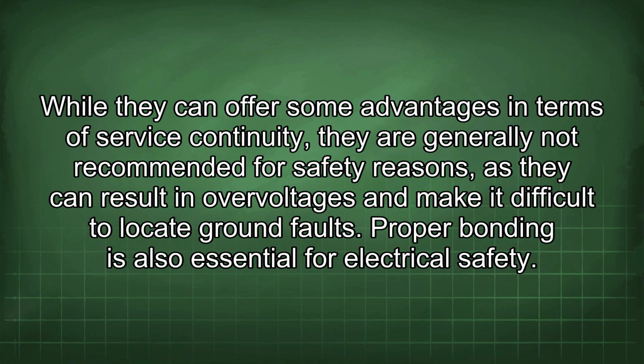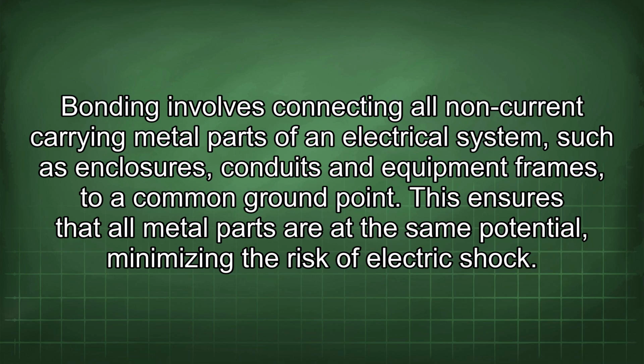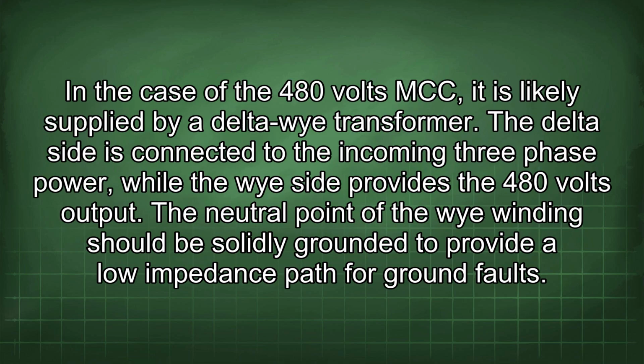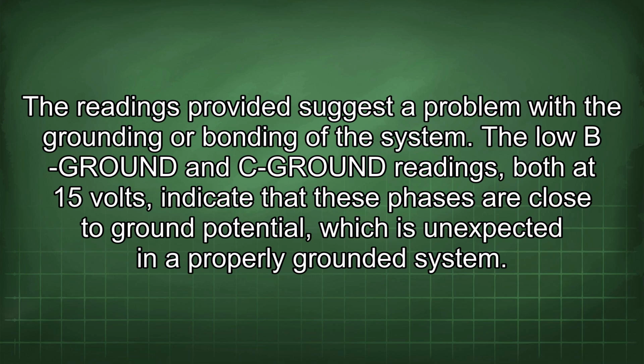While they can offer some advantages in terms of service continuity, they are generally not recommended for safety reasons, as they can result in overvoltages and make it difficult to locate ground faults. Proper bonding is also essential for electrical safety. Bonding involves connecting all non-current carrying metal parts of an electrical system, such as enclosures, conduits and equipment frames, to a common ground point. This ensures that all metal parts are at the same potential, minimizing the risk of electric shock. In the case of the 480 volt MCC, it is likely supplied by a Delta-Y transformer. The delta side is connected to the incoming three-phase power, while the Y side provides the 480 volt output. The neutral point of the Y winding should be solidly grounded to provide a low impedance path for ground faults. The readings provided suggest a problem with the grounding or bonding of the system.